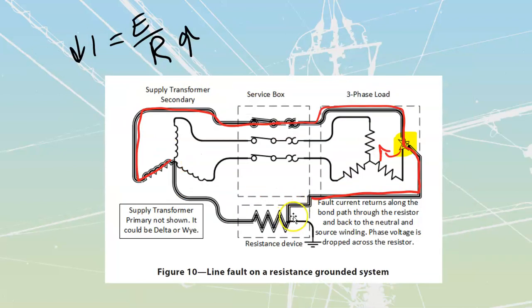It has to always be on the ground side of the resistor. Phase voltage is going to be dropped across the resistor as well. If you take a look at this, you can see that I've got just the voltage of the single phase impressed across here. And if I look, this side is connected to ground, 0 volts. This side is connected to my phase, which would mean it would have to drop the full value of phase voltage. So I would see this point rising to the phase value of voltage. If we had that 4160, 2500, that would mean this point here would be at 2500 volts—which is why we need to make sure that this conductor all the way along here is going to be insulated.